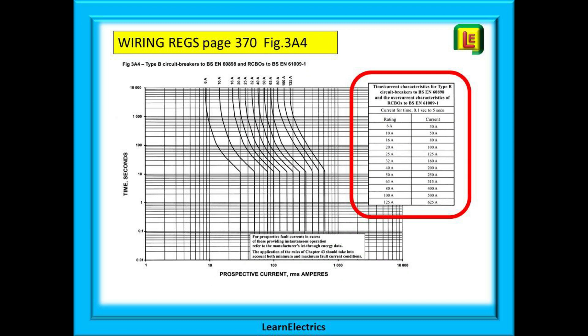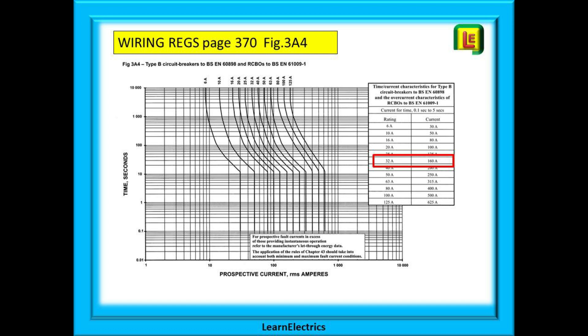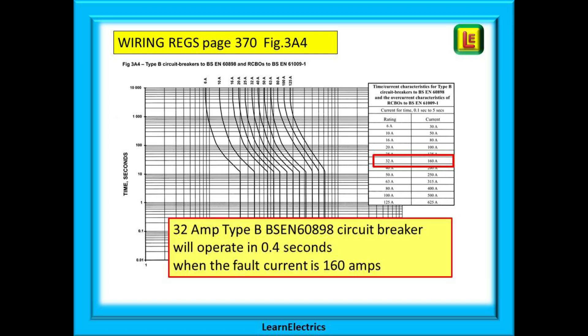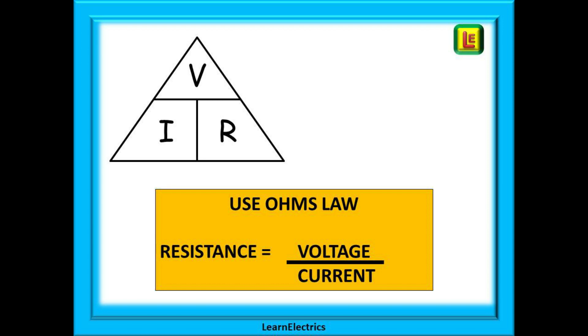Look now at figure 3A4 in appendix 3 of the wiring regulations, on page 370. This page is specifically for type B circuit breakers and RCBOs. We are interested in the chart on the right-hand side. The chart heading tells us it gives figures for any disconnection time between 0.1 seconds and 5 seconds, so our 0.4 second requirement fits neatly into it. Our circuit breaker is 32A — the left column — and the right column tells us that this size of device needs 160A of fault current to pass through it to achieve that 0.4 second disconnection time.